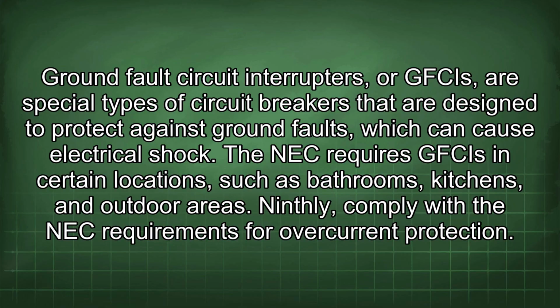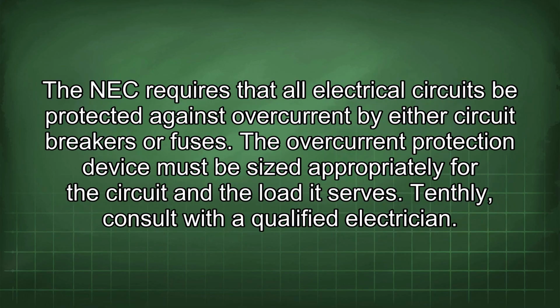Ninthly, comply with the NEC requirements for overcurrent protection. The NEC requires that all electrical circuits be protected against overcurrent by either circuit breakers or fuses. The overcurrent protection device must be sized appropriately for the circuit and the load it serves.